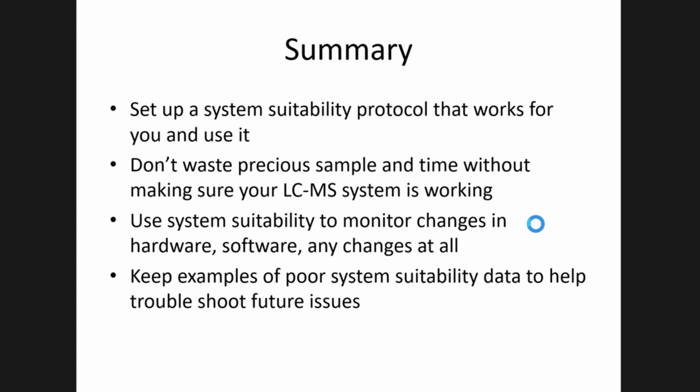Yeah, so I can tell you what I do. I don't know if it's totally right, but it's what I can defend. When I have a system suitability standard, I run heavy labeled peptides spiked into a sample matrix that is similar to the samples that I would analyze. So I use a lysate digest with heavy peptides spiked in. I target those heavy peptides and I track those over time on the triple quad.